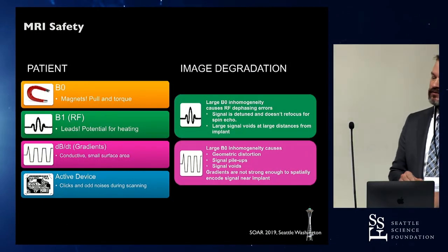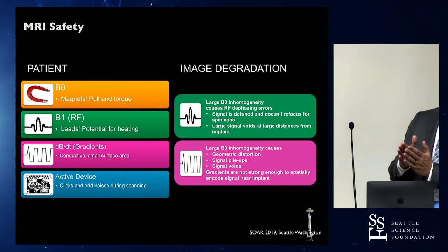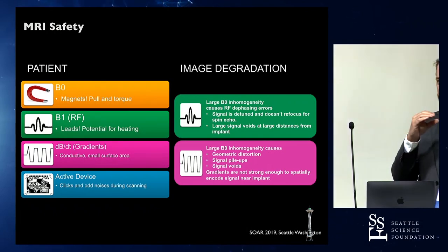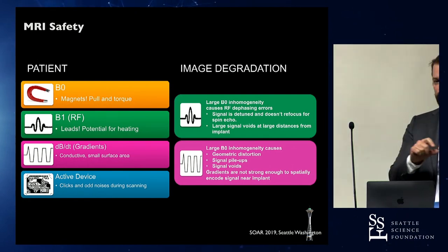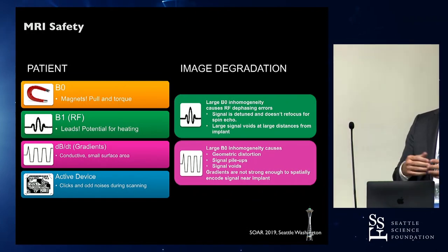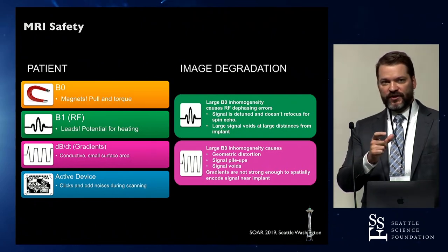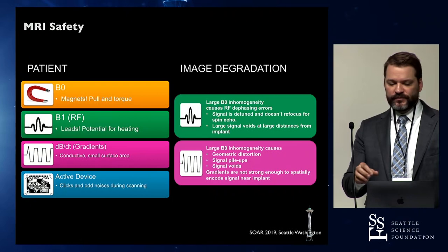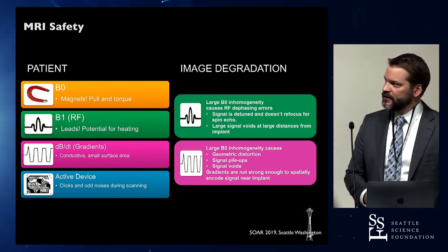What can happen to a cochlear implant magnet inside an MRI scanner? First, when the internal magnet tries to align with the static field, it can pull hard and cause pain. It can also twist the magnet — actually pop it out of its silicone sleeve or casing. Second, the alternating radiofrequency pulse in a wire can cause an alternating current, which generates heat due to resistance in the wire. The cochlear implant electrode is insulated in silicone except at the contacts, so all heat would be given off inside the cochlea, running a risk of injuring spiral ganglion cells.